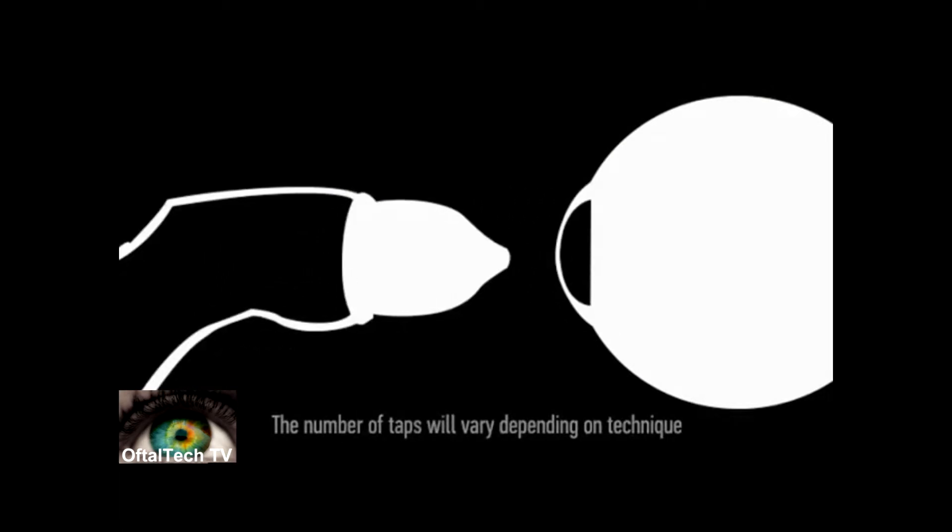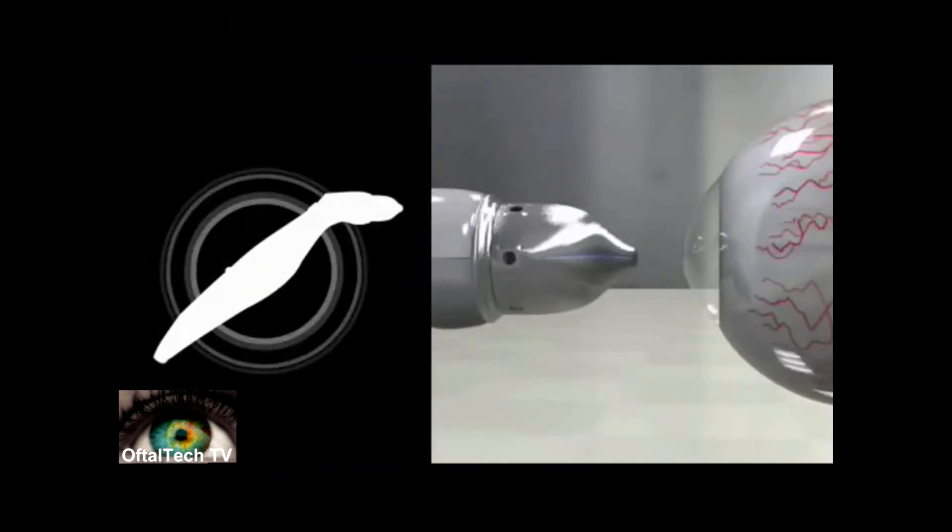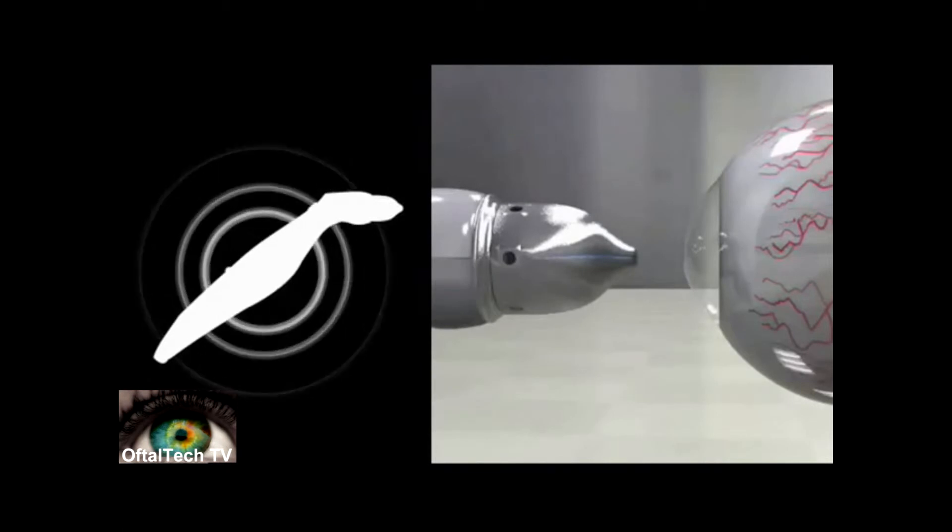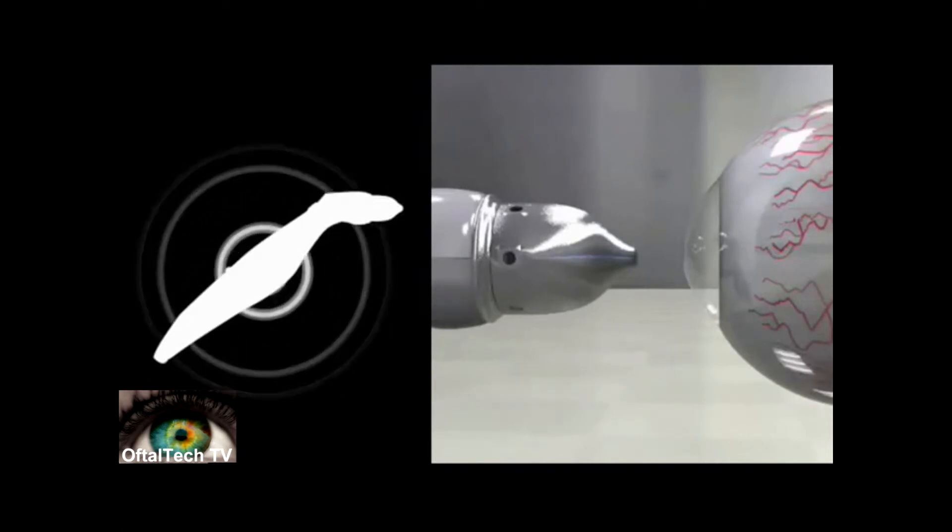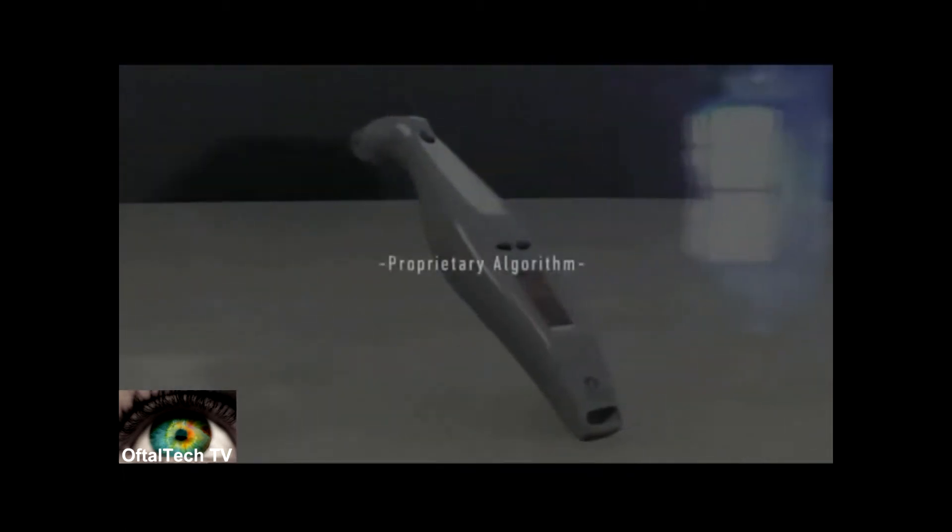As you gently tap the cornea, you will hear short chirps followed by one longer chirp. The longer chirp indicates you have obtained an IOP measurement. The number of short chirps can vary. The AccuPen has a proprietary algorithm which eliminates the need for a confidence factor.